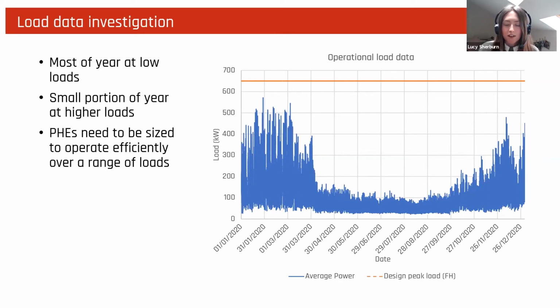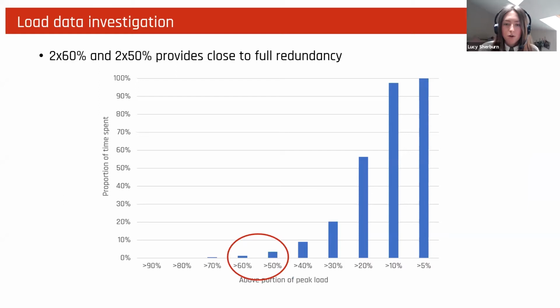And if you're having a plate that is sized at peak load and actually you're only operating at 10, 20% of that, you're going to start seeing that laminar flow and have that reduced amount of turbulent flow. Next slide, please. We also looked at the proportion of year spent above a percentage of peak load. So you can see with the above 20%, there was 55% of the year spent above 20% of peak load, but that also shows 45% of the year was spent below that. So large portions spent again at low load.